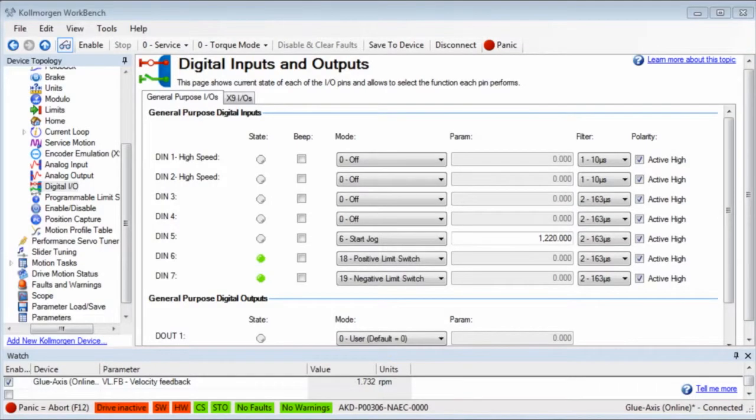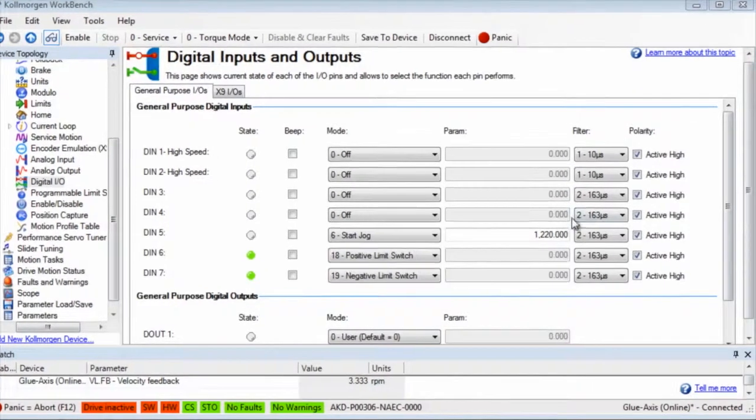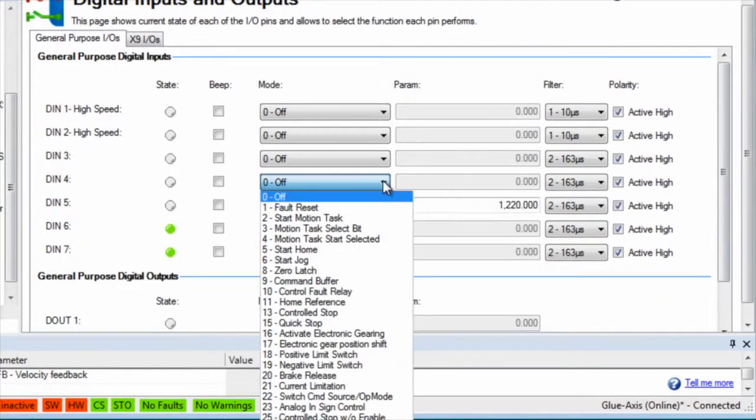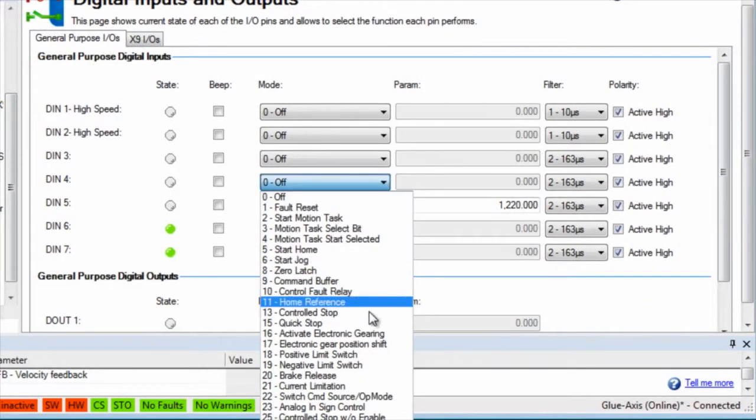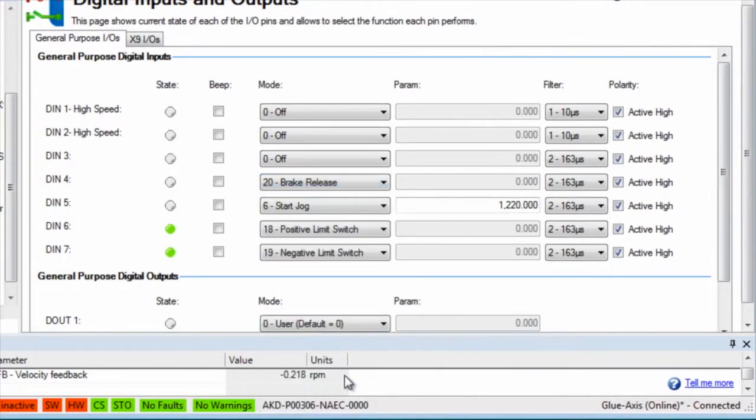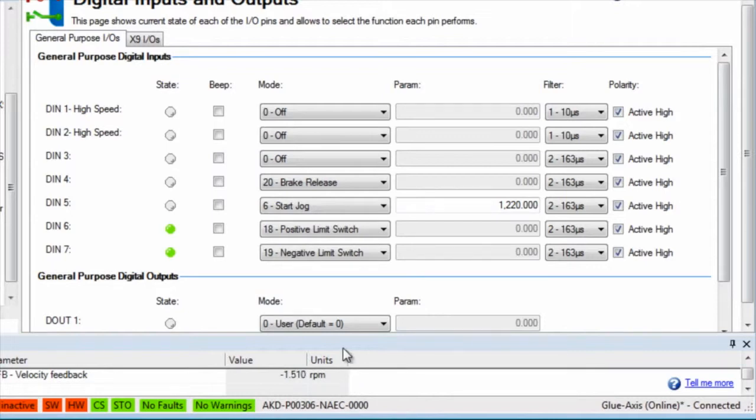Digital input 4 is set to 20, brake release. In applications with a failsafe brake, it might be necessary to disable the drive and remove the brake. Since the brake is on when the drive is not active, this will allow the brake to be removed.